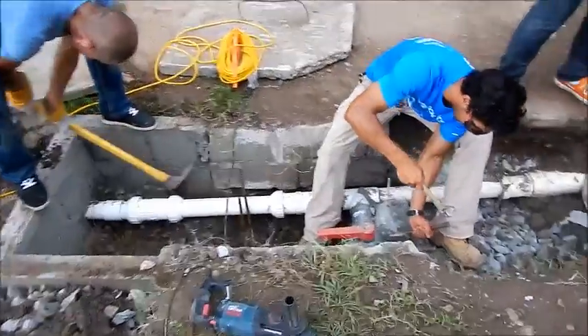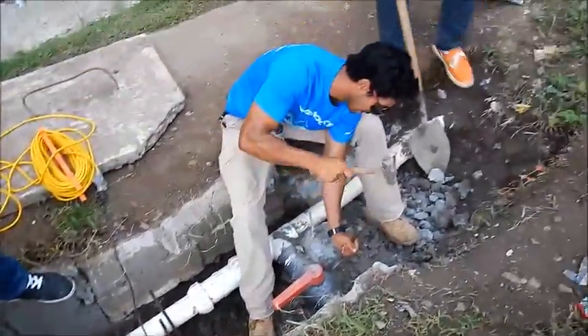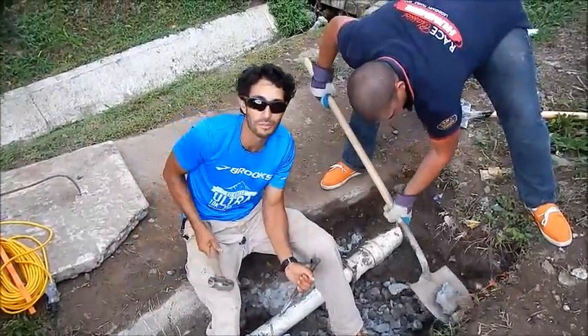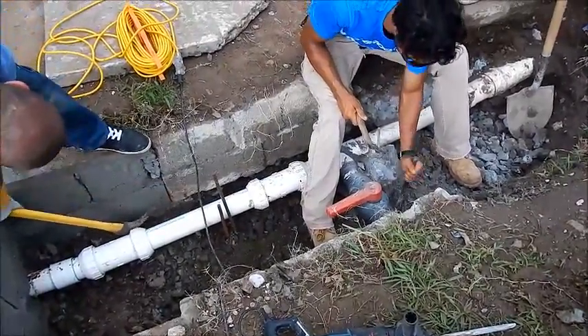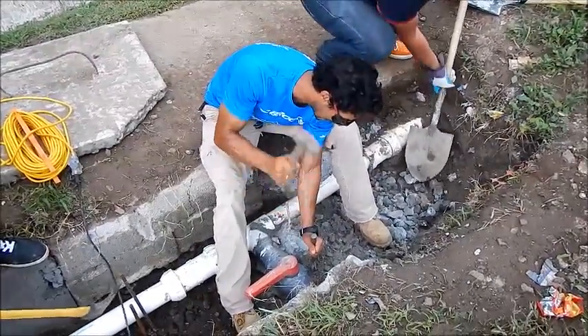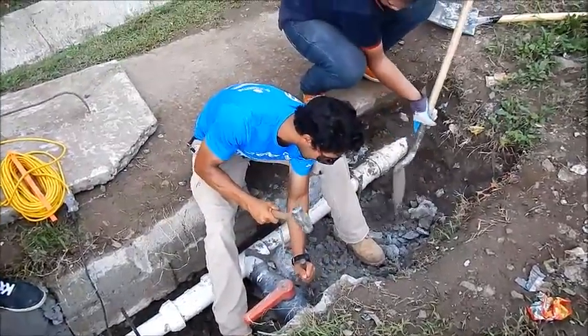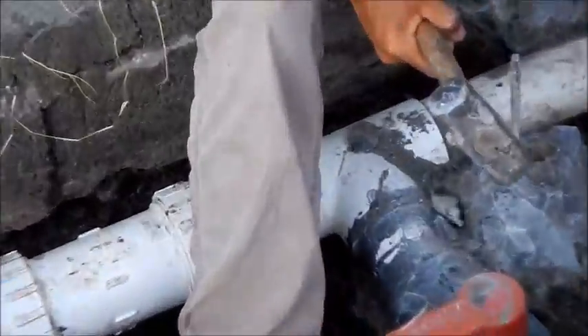This is the valve box — we've probably rebuilt this valve box about six times. Unfortunately we tried to put three 3-inch lines and bring them into one spot, but the schedule 20 pipe and the PVC fittings just couldn't take it, so we had to redistribute the loads. Now the fitting actually split open — cracked — and it's got to be from pressure.